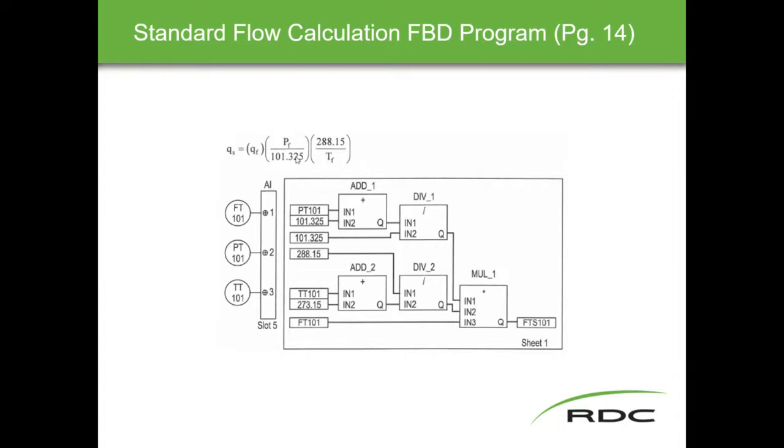What is going on? It looks like on that function block, they want to add those two together for some reason. But you should be dividing those. Well, no, because I should have a different formula here, because this is gauge pressure. So we're doing gauge pressure plus atmospheric pressure and then dividing. That would be the correct formula, but I guess this is the wrong formula, so I have to fix that. So this is gauge plus atmospheric in order to get us into absolute pressure, and then we're dividing it by atmospheric pressure. So that's this function right here.